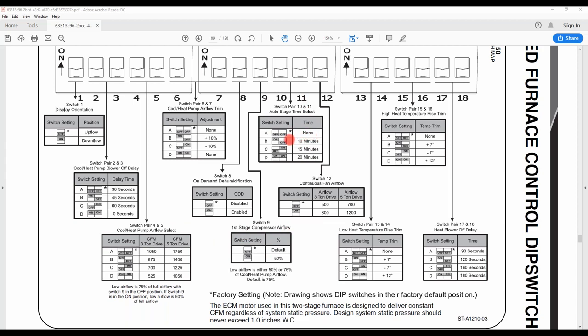So number 10 and 11 come factory set in the off position. If you have a single stage stat, you wire it down to W1 on the control board. If you do not change 10 and 11, you leave them in the off position and you're only wired to W1, you will never come out of first stage. If you take 10 and flip it to on, your unit will fire up. It'll go to first stage for 10 minutes. After 10 minutes, it'll then go to second stage. Same is true for 15 minutes or 20 minutes, depending on your timing that you want for your application and design. So that is only used when you have a single stage thermostat.